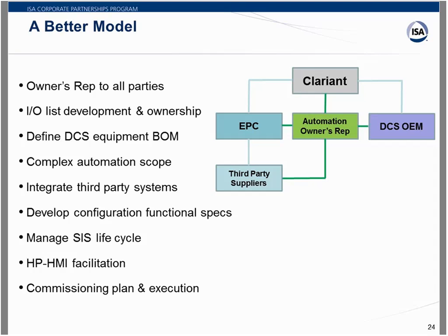So to do the parameterization on each device and figure out which parameters were of value and needed and which handles the control system should manipulate in the device is a rather large task when you have that many programmable devices involved. The automation owner's rep also took over integrating the third-party systems to make sure that what they were supplying was going to integrate into this overall control system.